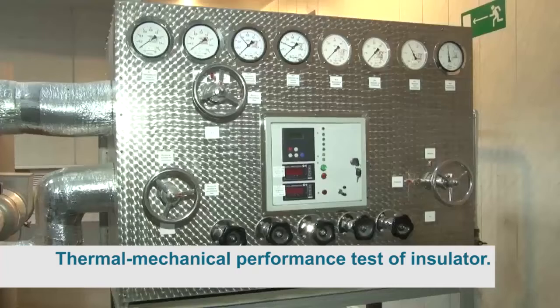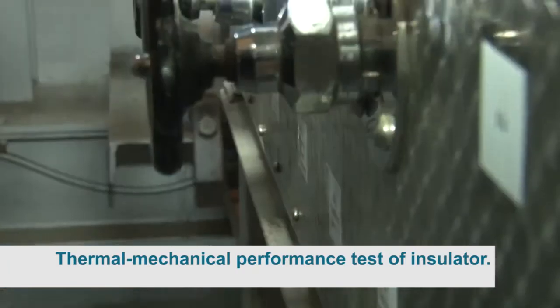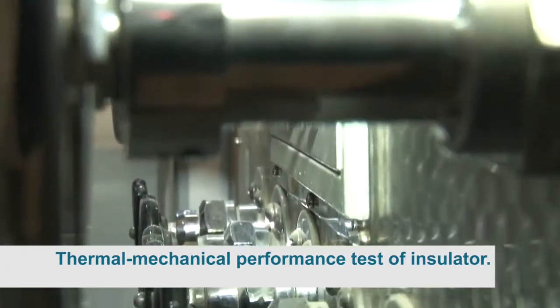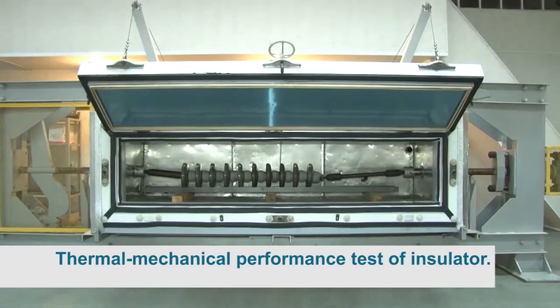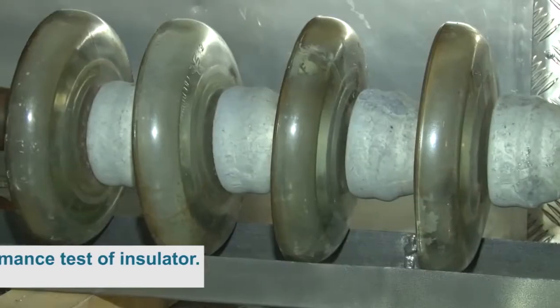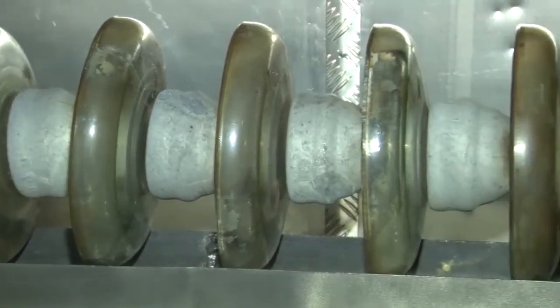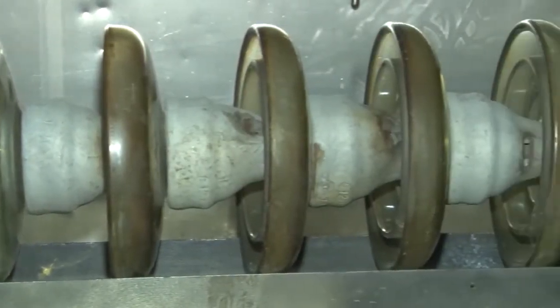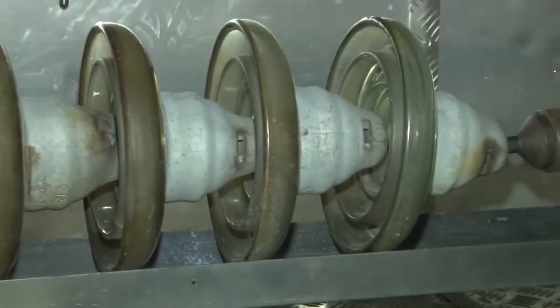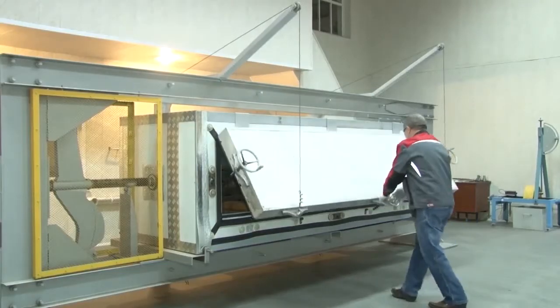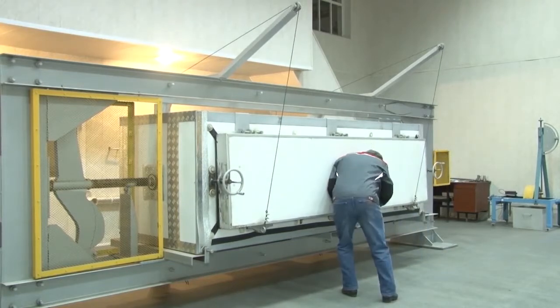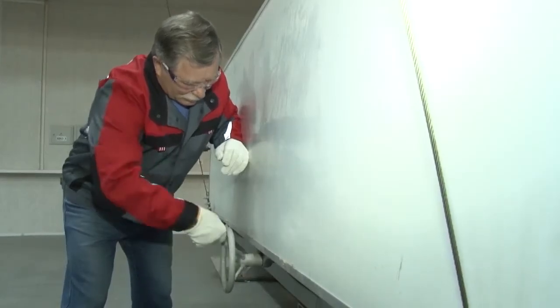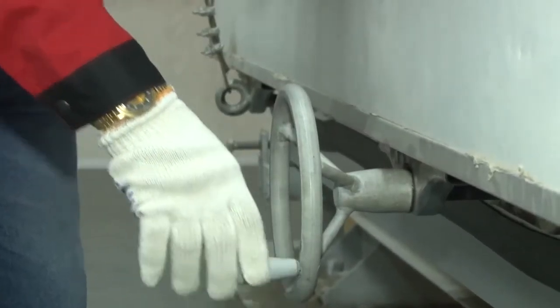Thermal mechanical performance test of insulator type PS12A. Glass suspension insulators of type PS12A are in accordance with the IEC standard. The measured value of the failing load occurred between 156 and 183 kilonewtons, while the standard measure is 120 kilonewtons. The insulator of type PS12A meets the IEC requirements.